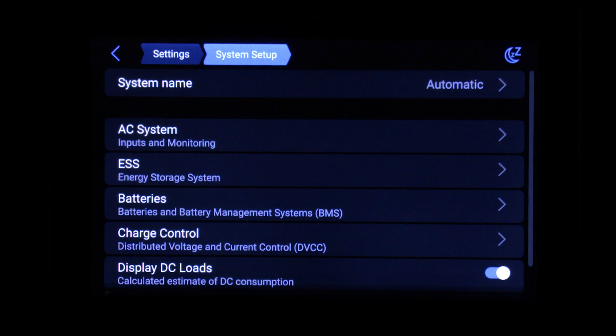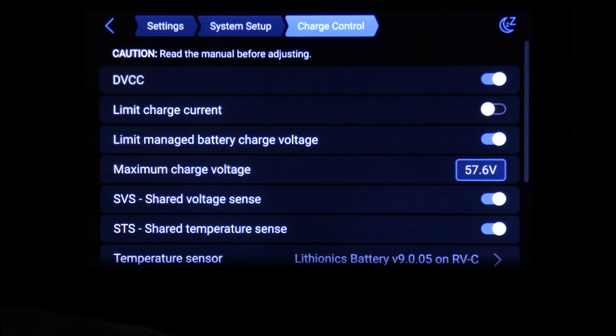One important setting to be aware of under system setup is the charge control, that's distributed voltage and current control. You want to make sure that's always enabled. That allows the Lithionics BMS to control the charge voltage and charge current across all devices on the bus. It is possible to override the maximum charge voltage - I haven't tried that to see how it works - but the most important thing is to make sure DVCC is always enabled and that the Lithionics battery is set as the controlling device.